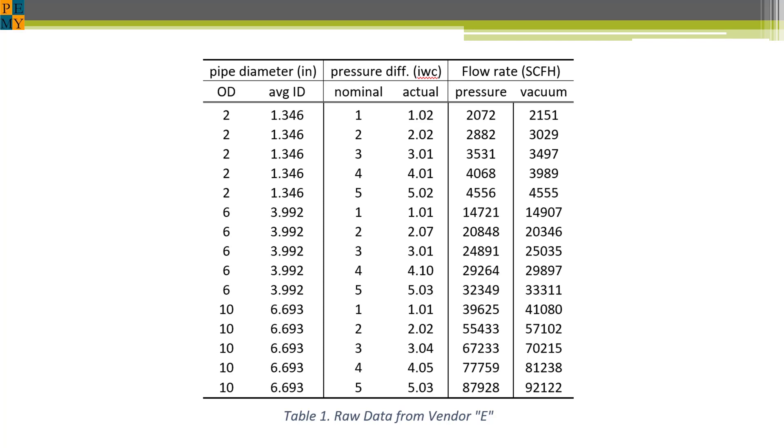The results were that large discrepancies that one would think would not exist do in fact exist. The flow rates under identical conditions range from minus 8.7% to 6.2% of the mean, or just about 15% from high to low. These disparities cast doubt on the manufactured flow certification processes and claims related to their PV valve performance.